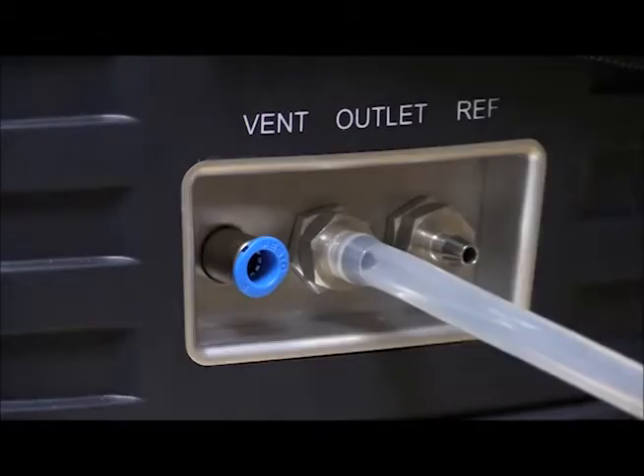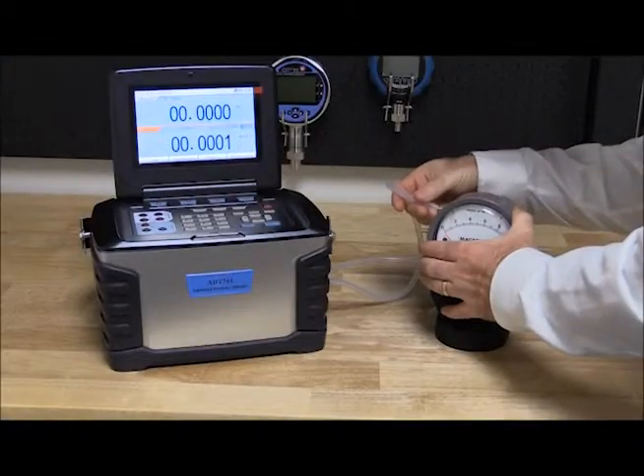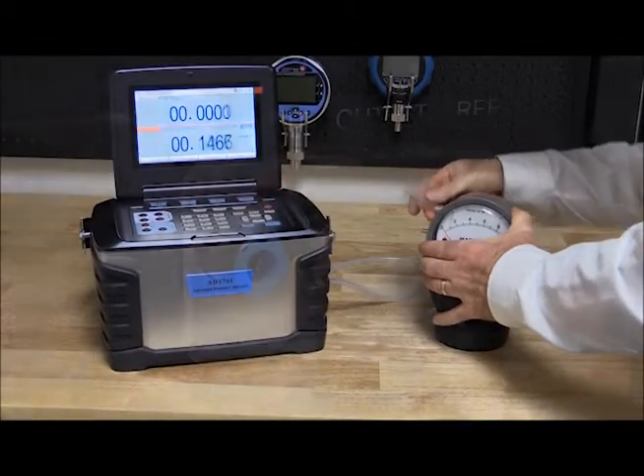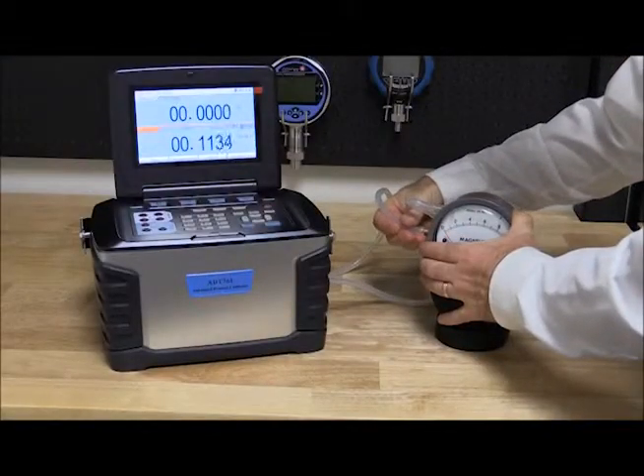The outlet port of the 761 is connected to the high port DUT. Then, the reference port of the 761 is connected to the low port of the gauge.